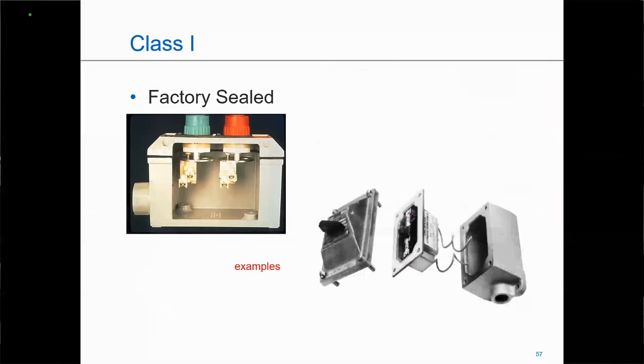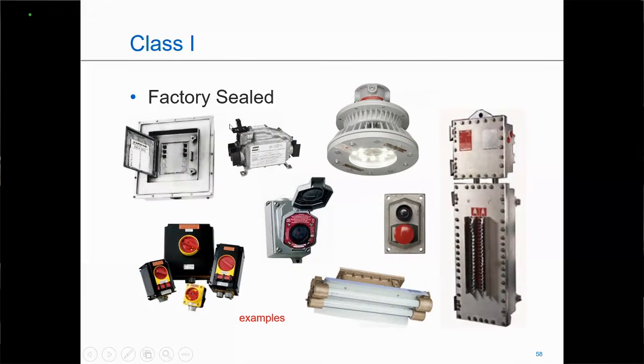We also have factory sealed. Here, when I'm factory sealing, the sealing is integral to the product. So we see some factory sealed contact blocks. Here's a sealing well that makes the product factory sealed. This is going to eliminate, except for a couple of exceptions you might find, the requirement for the external sealing fitting. You may also find times when a circuit breaker has a housing around it, or that it's encapsulated. You might find lighting fixtures, luminaires that are factory sealed, or when I have a piece of equipment that has my terminal housing and my housing that's required to be explosion-proof, you'll have factory sealing done between those two areas.